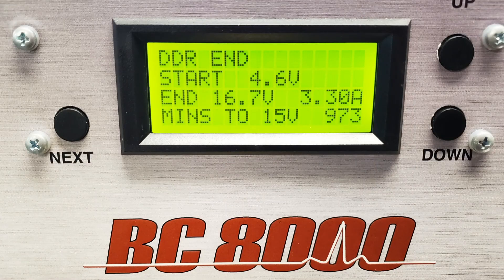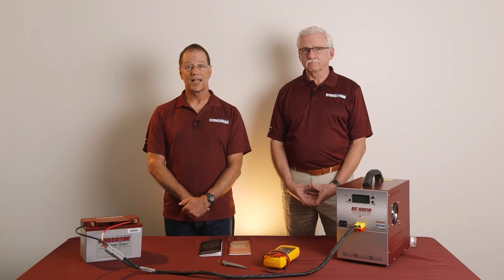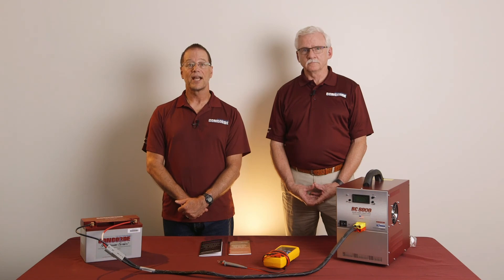On the screen is a picture of the display after the DDR procedure was performed. This display shows that the battery started at 4.6 volts and ended at 16.7 volts. It took 973 minutes or 16.2 hours to reach the trigger voltage of 15 volts. After the DDR charge is completed, the next step will be to perform a capacity test. The DDR charge will often recover the battery sufficiently to pass the capacity test, but there is no guarantee. The sooner the DDR charge is done after the battery is deeply discharged, the better the chances are of passing the capacity test. For instructions on doing the capacity test, refer to the separate training video on capacity testing.